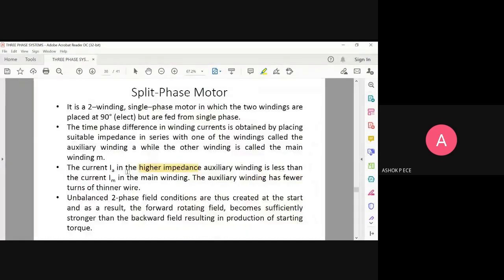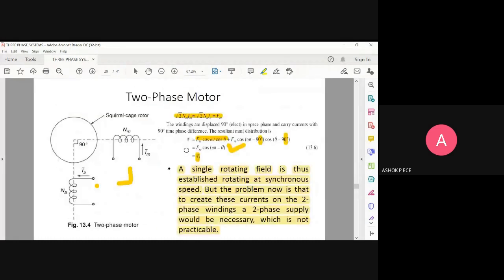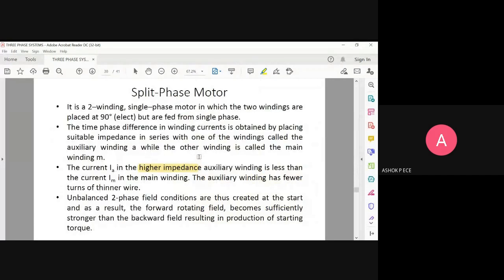When everything is perfectly balanced, you will get only a single field. But since the two windings are completely different, you will have two fields — the forward rotating field and the backward rotating field. The forward rotating field will be much stronger than the backward rotating field.